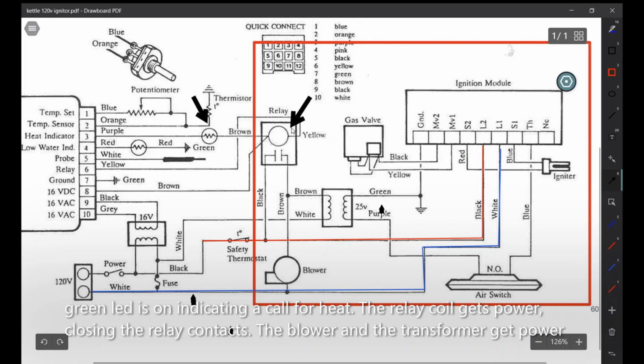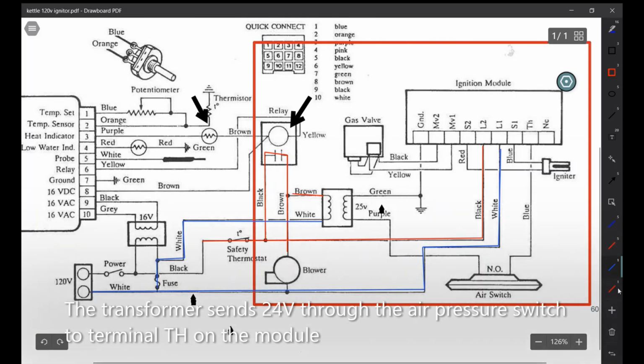The relay coil will get power, which means we're going to get power through this relay and to our blower. So now our blower turns on. And at the same time, we're going to get power at our transformer. Next, our air pressure switch will prove. So if our blower motor's running, we're going to get 24 volts coming in our switch and out of our switch. And we're going to go up to terminal TH.